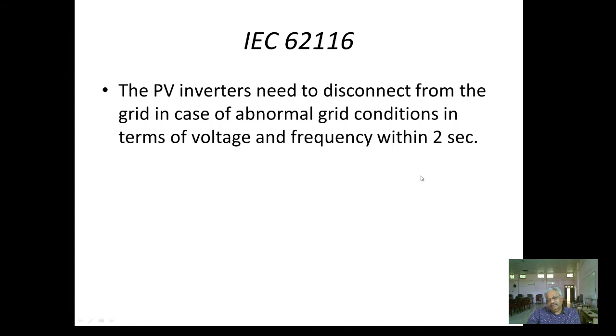If you look at standards such as IEEE 1547, it says that distributed generation should be disconnected before 2 seconds after opening of an upstream device, because after opening of an upstream device, an island takes place. The reason is that before the upstream device recloses, you need to be able to detect that something upstream has opened and de-energize the DG. So you do not have a possibility of out of phase reclosing. We have seen how the voltages can be 180 degrees apart. This can be avoided because before reclosing of an auto recloser, you should get disconnected from the grid.